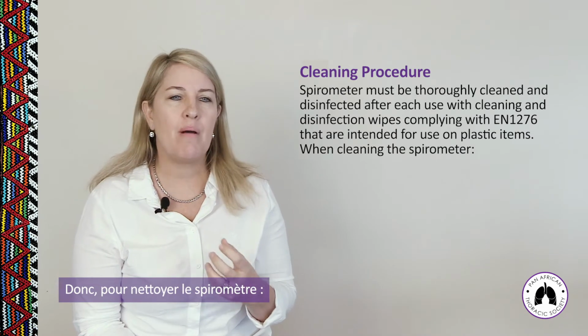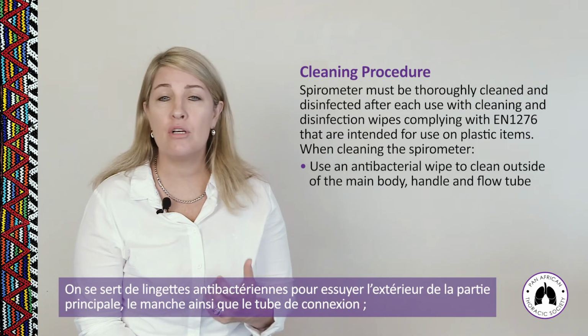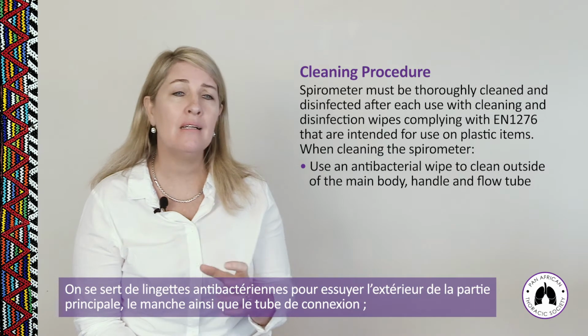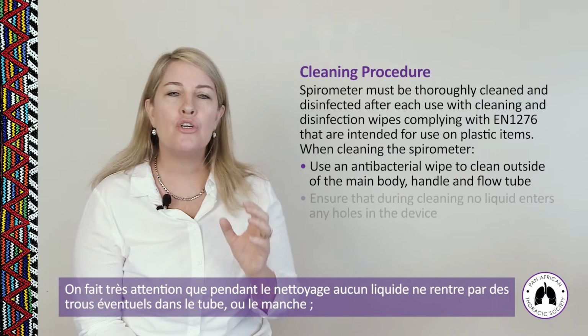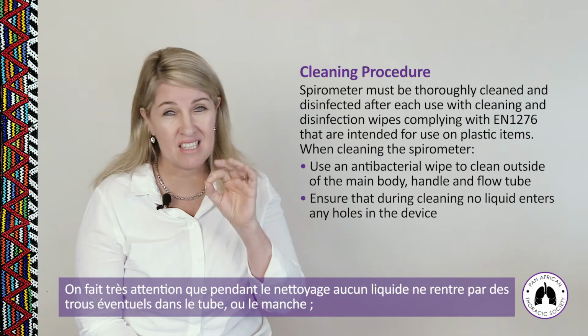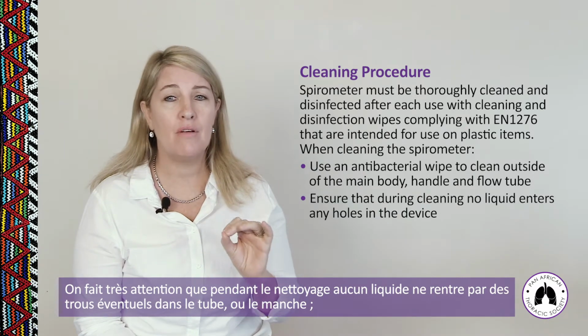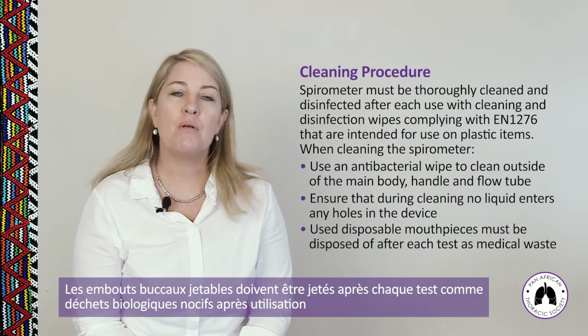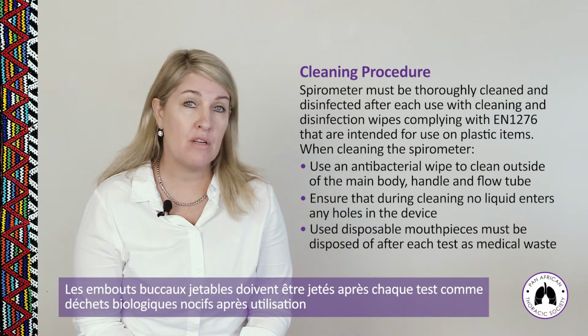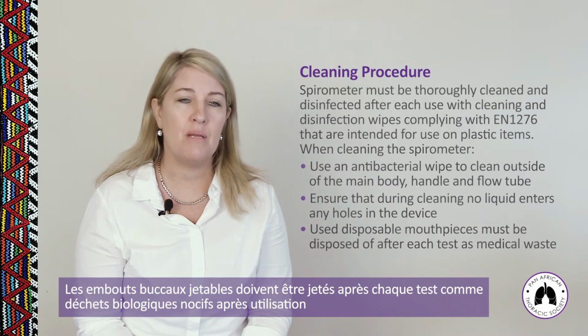When cleaning the spirometer, use an antibacterial wipe to clean the outside of the main body handle and flow tube. Ensure during cleaning that no liquid enters any holes in the tube itself and the handle. Use disposable mouthpieces, which must be disposed of into biohazardous waste after they've been used.